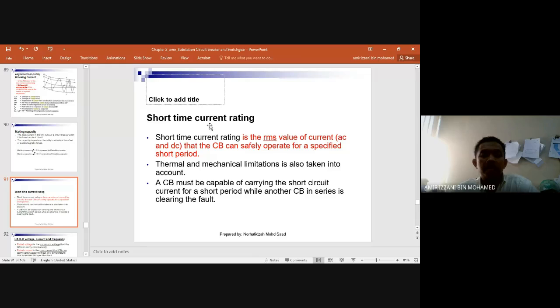Short time current rating. Short time current rating is the RMS value of current that the CB can safely operate for a specific short period. Thermal and mechanical limitations are also taken into account. A CB must be capable of carrying the short circuit current for a short period, while another CB in series is clearing the fault.